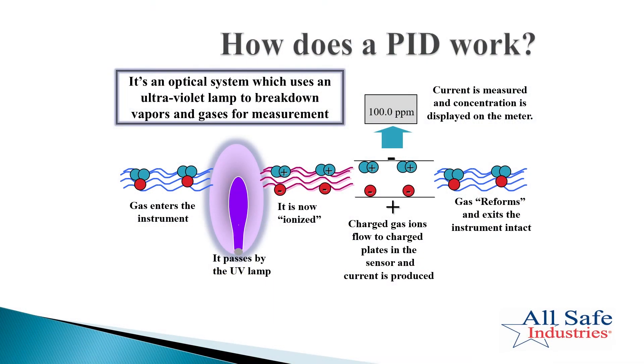So here's how a PID works. It's actually an optical system, meaning it's a light bulb. As gas enters the instrument, it's going to pass through ultraviolet light. The ultraviolet light will ionize the sample, meaning it's separating the positive and the negative particles. It will then attach to the detector plate in the instrument, and then the circuit board — the motherboard in there — will turn that into a number that we can understand and show that value on the screen. So that's where we get the name photo ionization detector — it just explains how the sensor works.